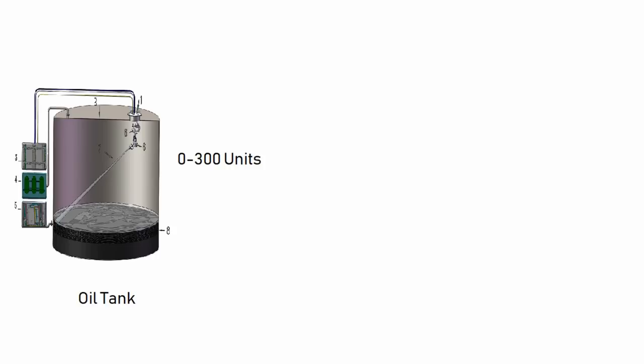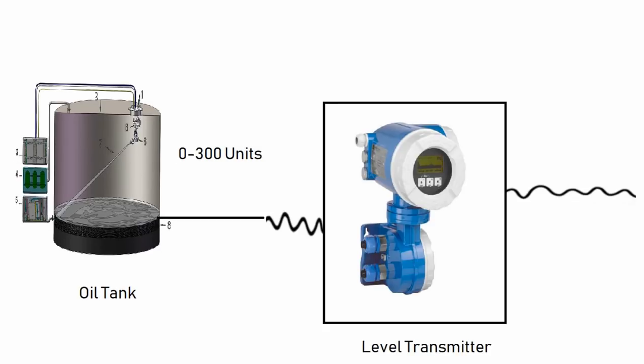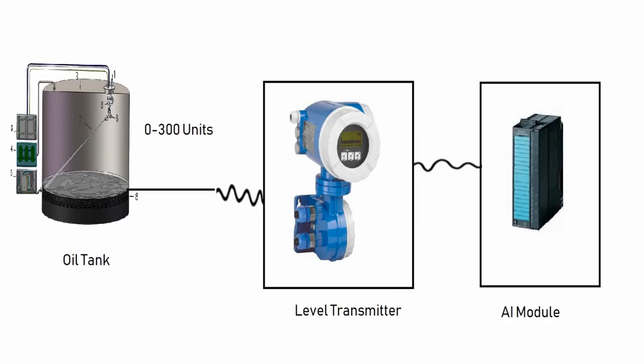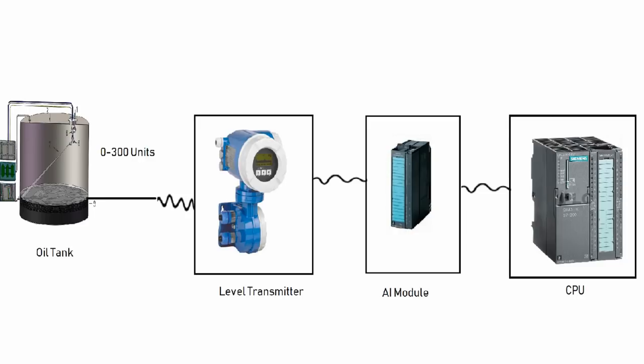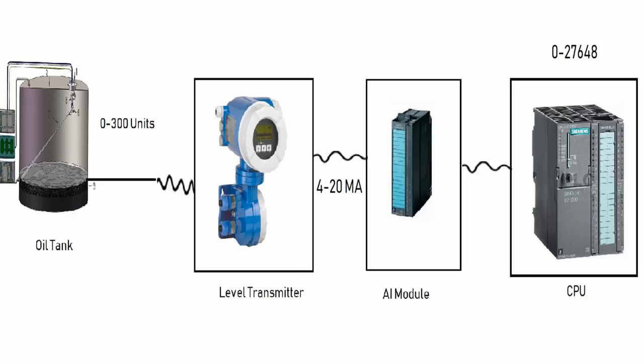We got an answer: the level range is 0 to 300 units. To measure that we put an instrument — a level transmitter — there to measure how much level is inside the tank. Then we need an AI card. For a digital signal we need a DI card, and for an analog signal coming from the field we need an AI module, and after that the CPU. That's how the signal processes from the oil tank to the CPU of the PLC.